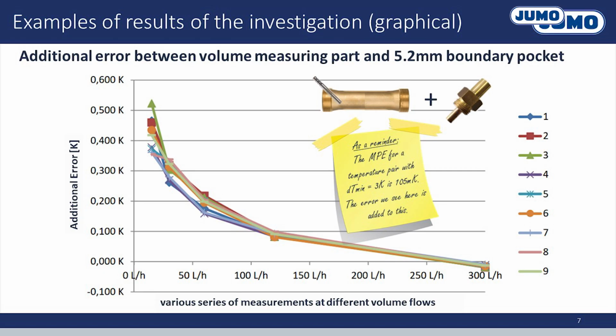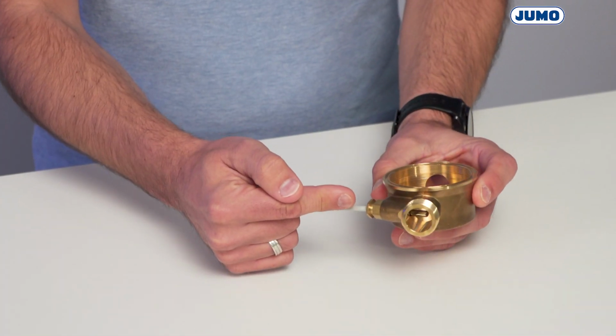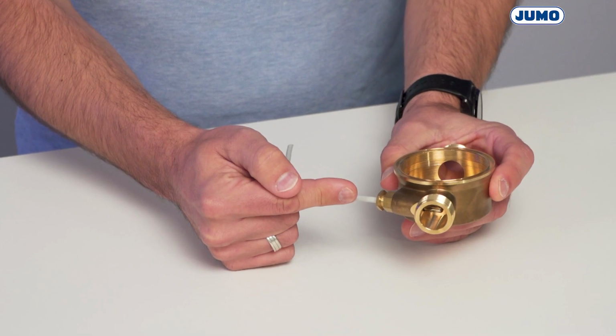This can be in the order of magnitude of 1 MPE or even significantly higher. This influences the measuring accuracy and, in the worst case, can lead to incorrect billing values. You might now ask yourself, why should you install asymmetrically at all if it can lead to errors? The answer often lies in the simplification of the installation. Many manufacturers of heat and cold meters already integrate a temperature probe in the volume measuring section, thus saving an additional installation point. This sounds practical at first, but is often associated with lower measuring accuracy if the other temperature probe is installed in a pocket.